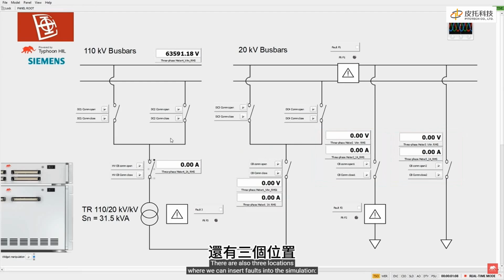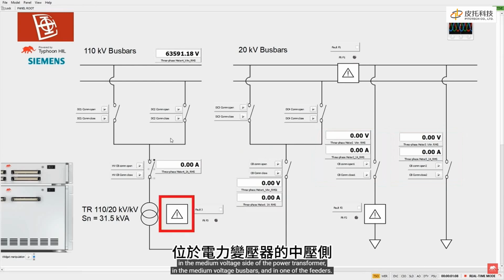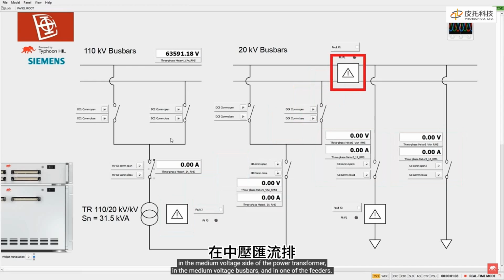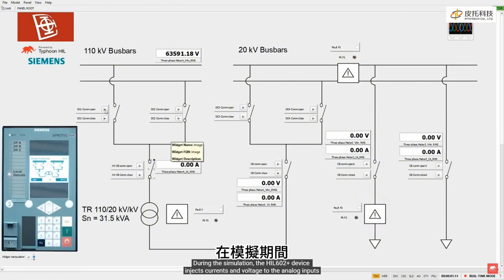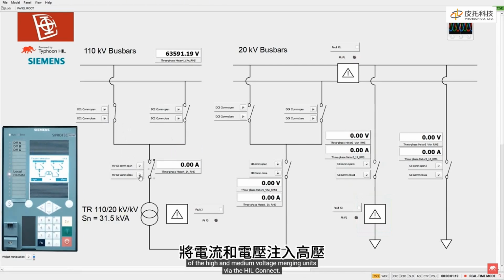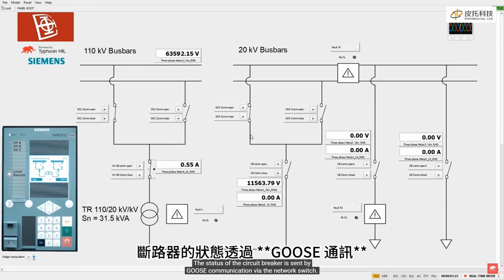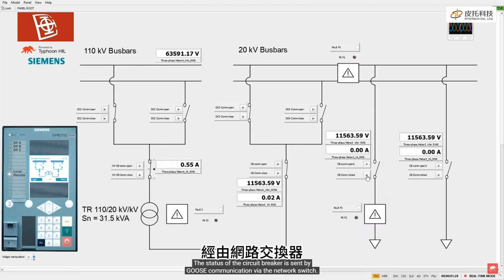There are also 3 locations where we can insert faults into the simulation: in the medium voltage side of the power transformer, in the medium voltage bus bars, and in one of the feeders. During the simulation, the HIL 602 Plus device injects currents and voltages to the analog inputs of the high and medium voltage merging units via the HIL Connect. The status of the circuit breakers is sent by GOOSE communication via the network switch.